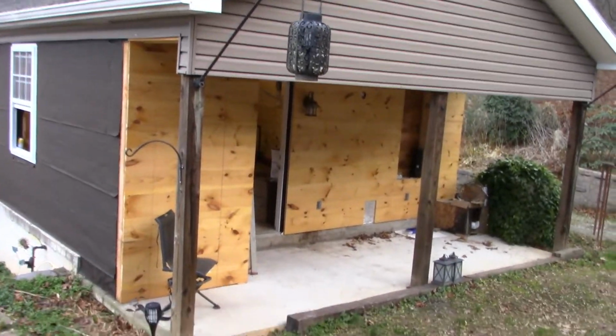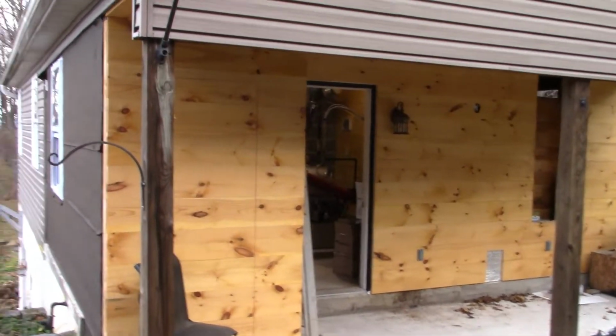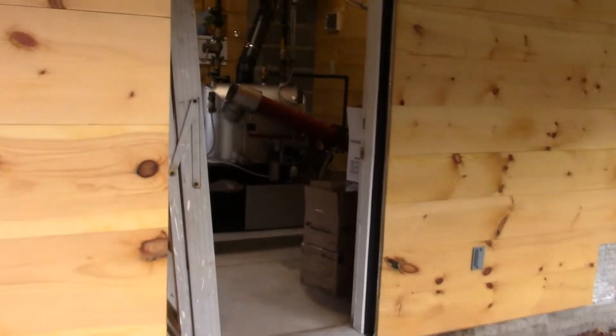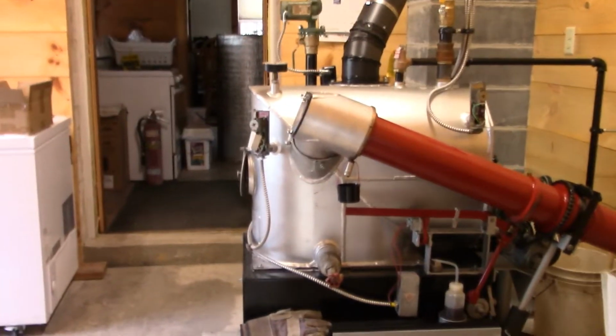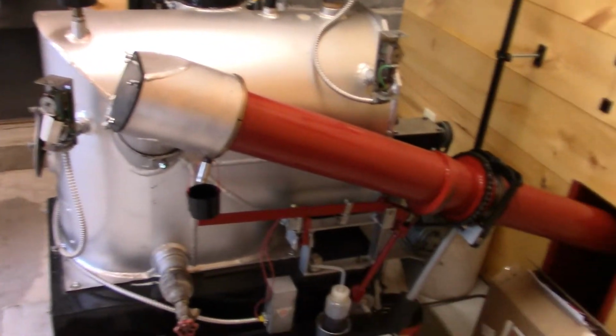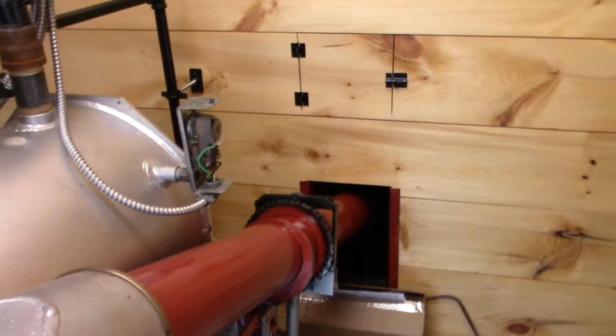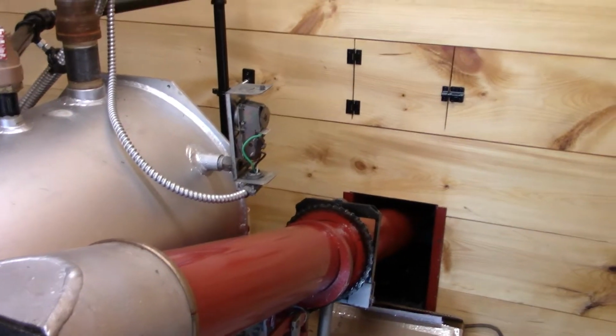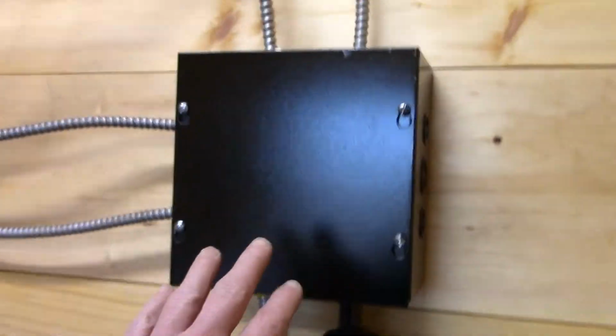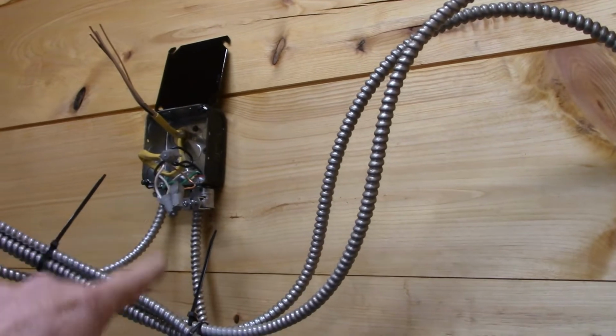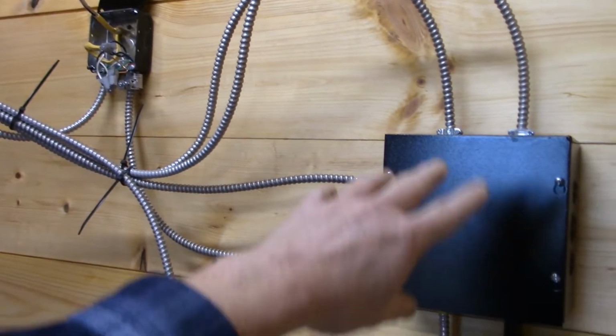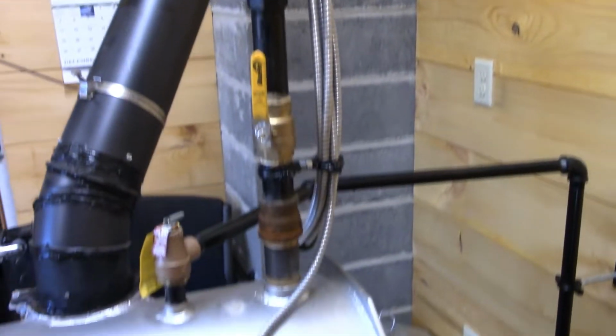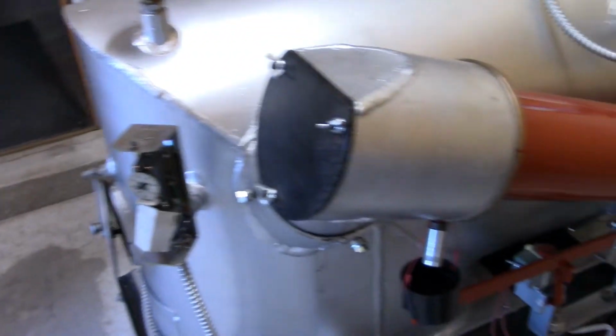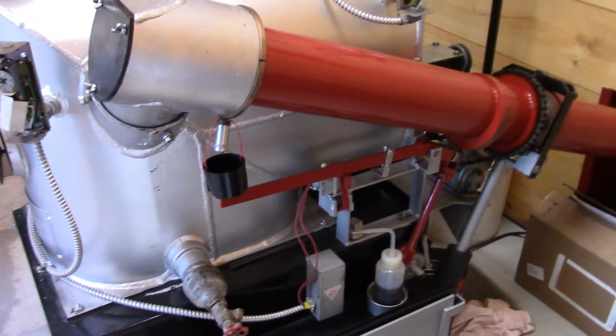Alright, so here's what we got going on inside here. The Axeman's just sitting here sleeping right now. Coal bin full of coal. It's just eating out of the coal bin. This is the main electrical box. This is where the electric comes in, and we run it over to this box, and then out to the various things that need to be powered on the Axeman, like the high limit aquastat, the anthrostat, pump, and the motor.